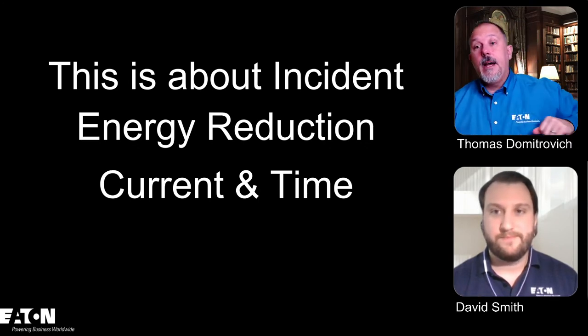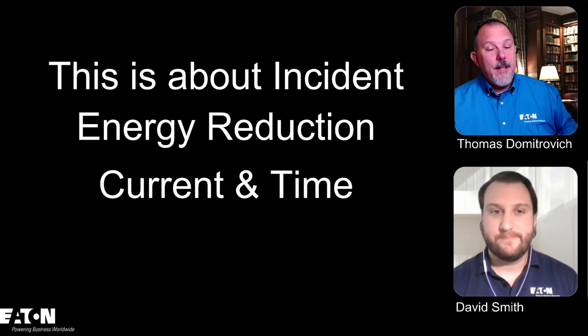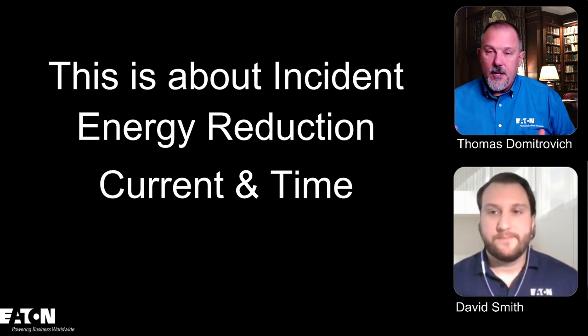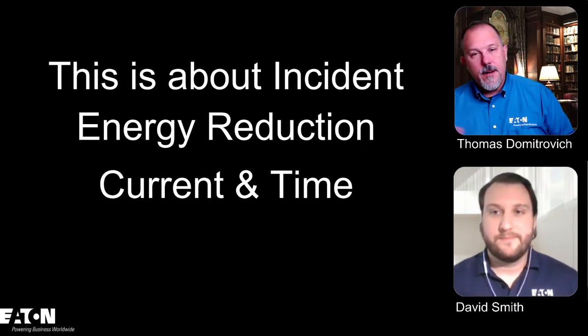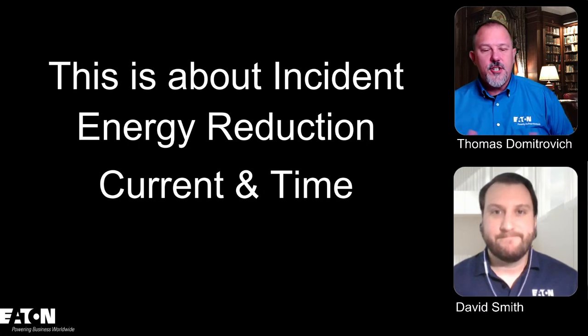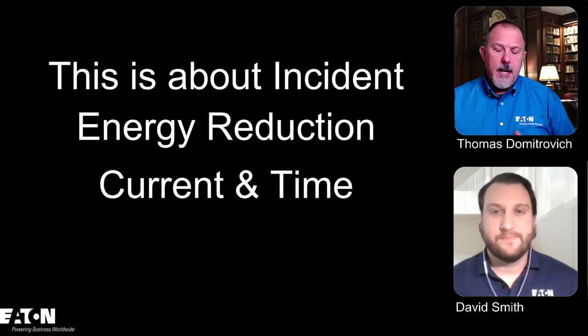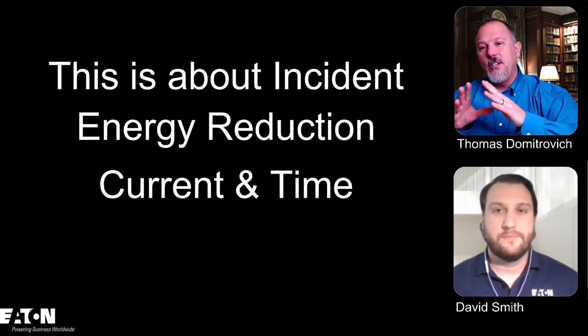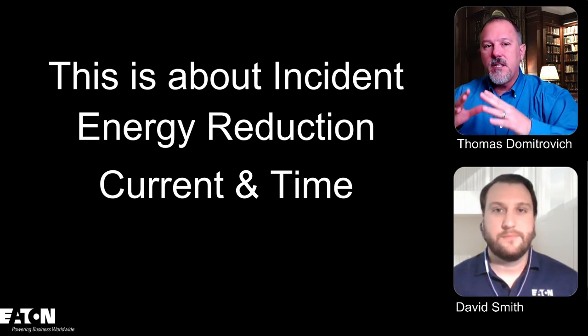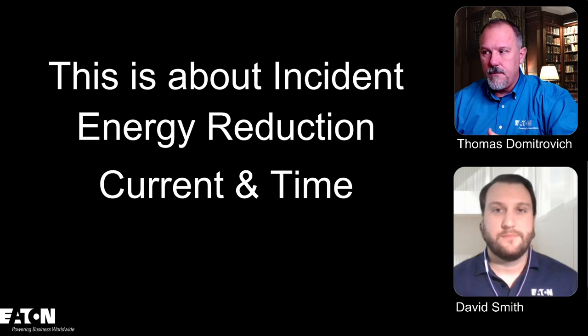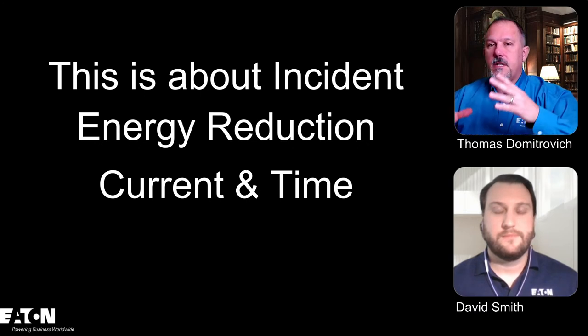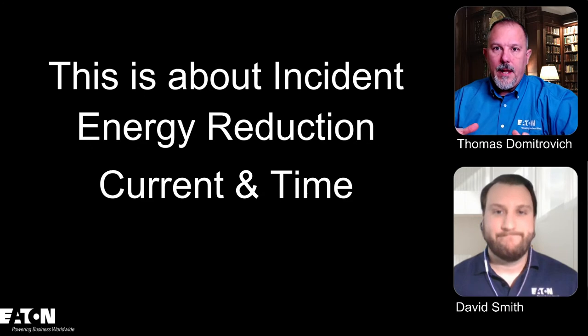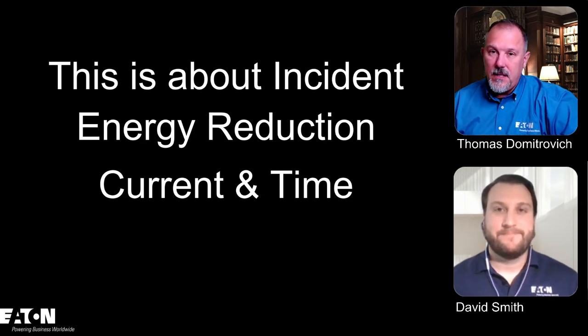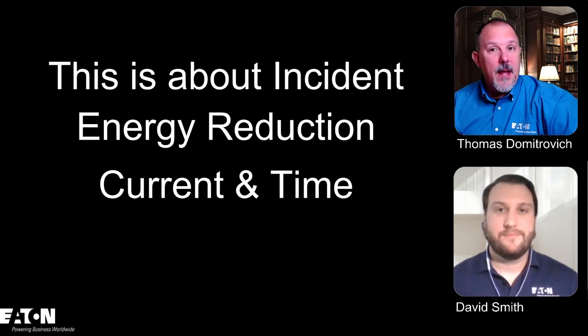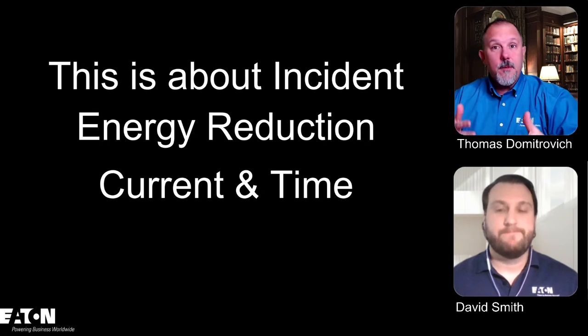Yeah, and to your point, everybody says higher available fault current, higher incident energy, not necessarily the case, because it's all about that clearing time. But the other factors, which I don't talk about because the National Electrical Code doesn't address them, are the size of the enclosure, which is not a significant impact but does have an impact, and the configuration of the bus.